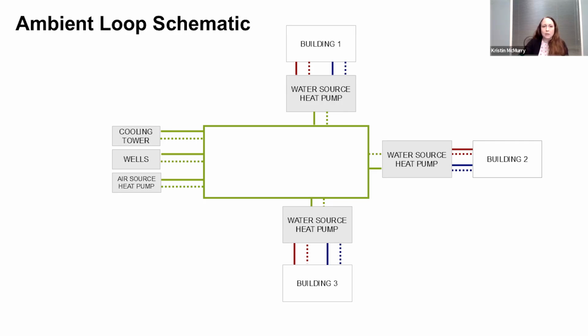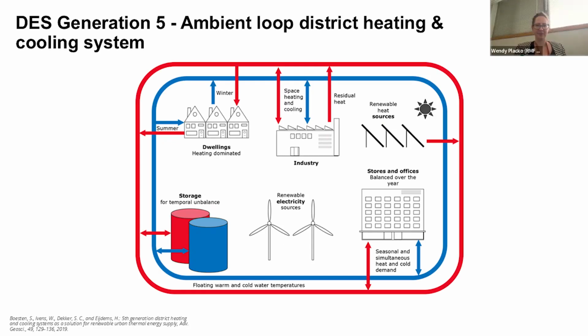If we go to the next one, that ties into what I was saying. You can get your heating and cooling from just about anything, including renewable heat sources that maybe didn't provide enough heat before but now can. One thing shown here that comes up a lot with ambient loop: you can use several different sources that don't all have to be located at the central plant. People often say that's the big deal with ambient loop, but I always say it's the smallest deal, because you can do that with any system. You could put a boiler in every single building and interconnect them if you wanted to.